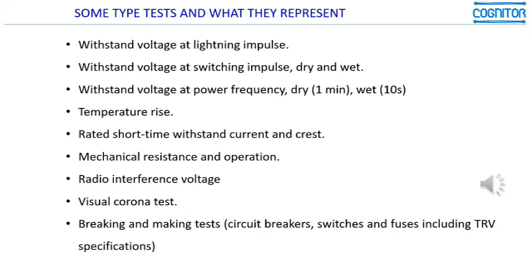Temperature rise test, which is a very important one to assure that the equipment will have the expected durability. The rated short time withstand current and peak, which is a test to demonstrate that the equipment is able to support the electrodynamical effects and thermal effects of the short circuits.